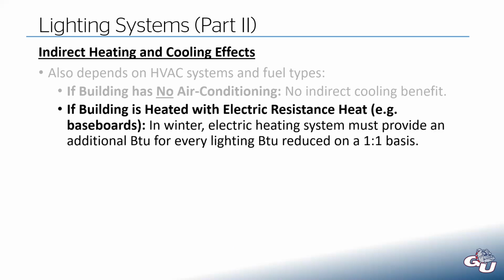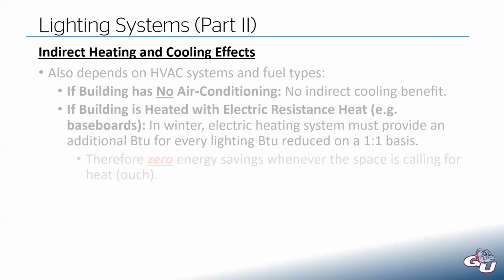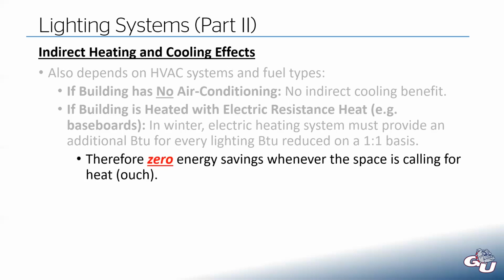Or if you have a building heated with electric resistance heat, like electric baseboards, which a lot of old houses have — in those winter months, that electric heating system has to provide an additional BTU for every lighting BTU we reduced. That means anytime you're in the winter months, you're seeing zero savings. Because if you reduce the wattage of your lights by 100 watts, your electric baseboard heat has to put out an additional 100 watts. So your net savings is zilch — and that's not a good look.